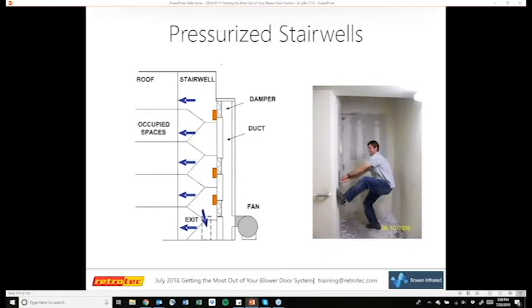So the first one is pressurized stairwells. In commercial buildings, especially like the test I did in Richmond, Virginia earlier this year with the big blower door test, it also needed a stairwell pressurization test. And a lot of times there's a permanent fan for stairwell pressurization in there. And so to really define where that needs to go or how that needs to perform, you can use a blower door to mimic how that's going to play out, to see how that stairwell pressurization fan is going to behave. And you can also use it to pressure match that fan to see how much pressure that stairwell pressurization fan is producing. So that's one commercial application for blower doors outside of just doing a blower door test itself.